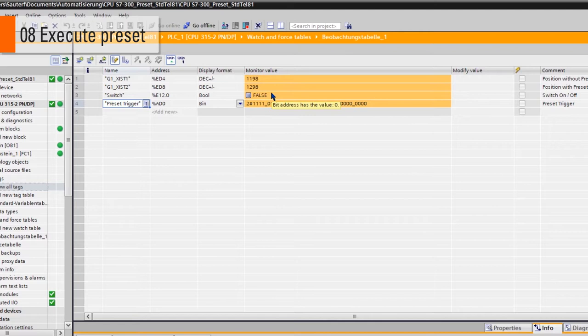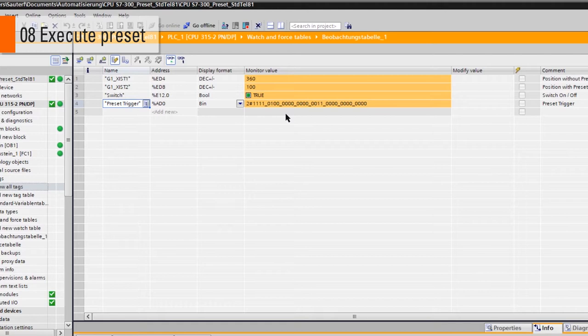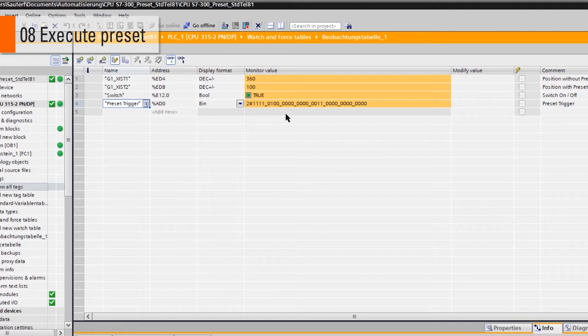If I turn the encoder and push my preset switch, the variable switch will appear as true. Now have a close look on the encoder position values XIST1 and XIST2. The first time only XIST2 will change to the value 100. XIST1 will remain unchanged.